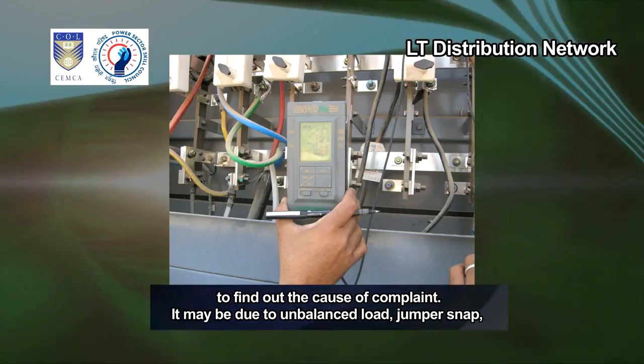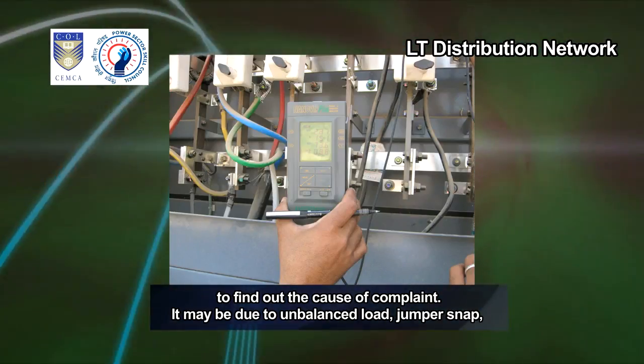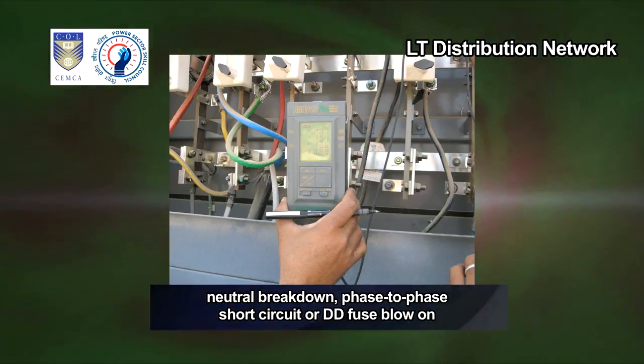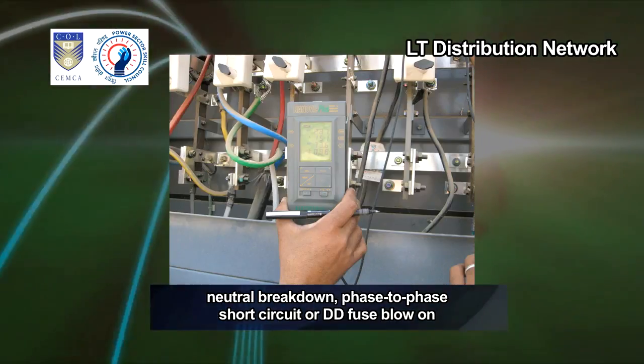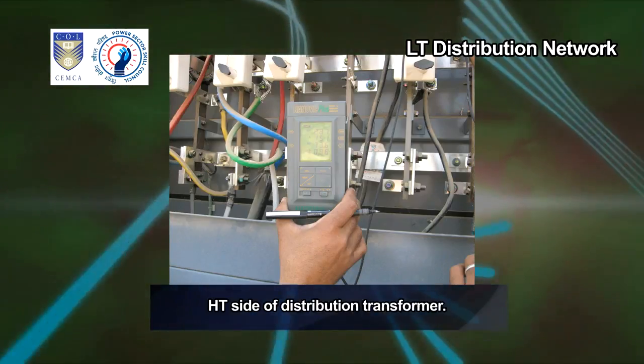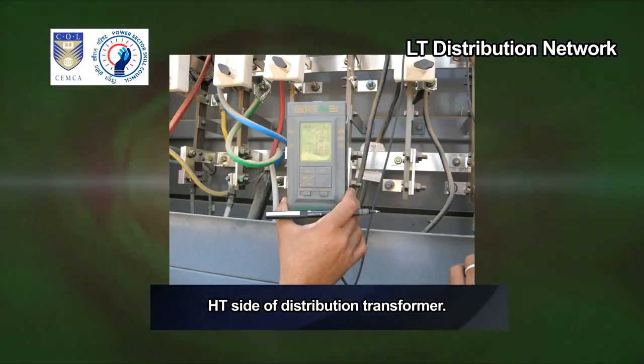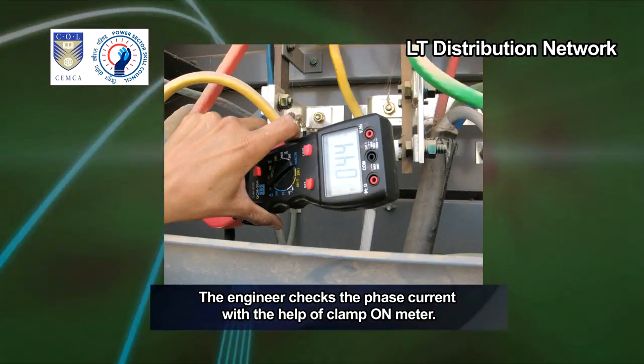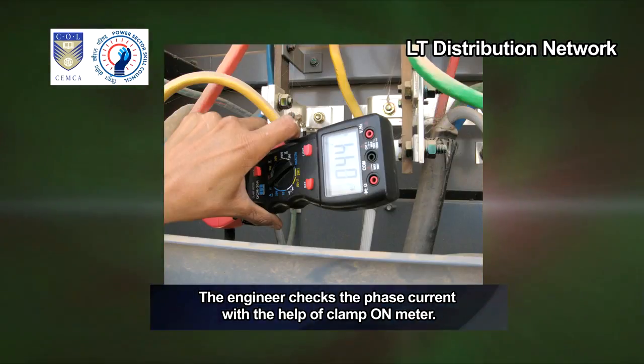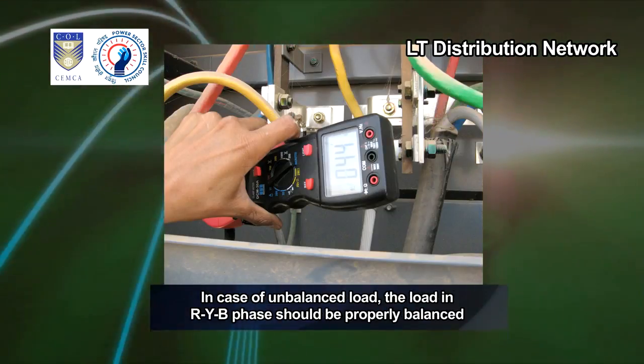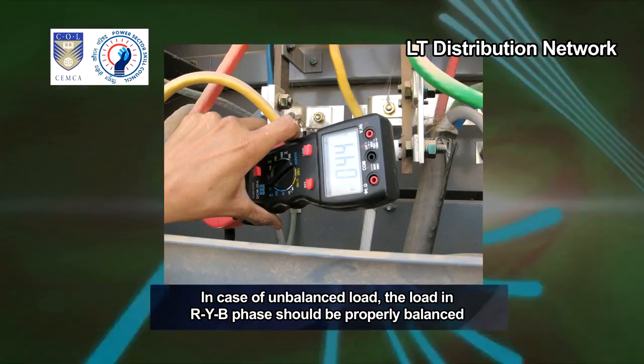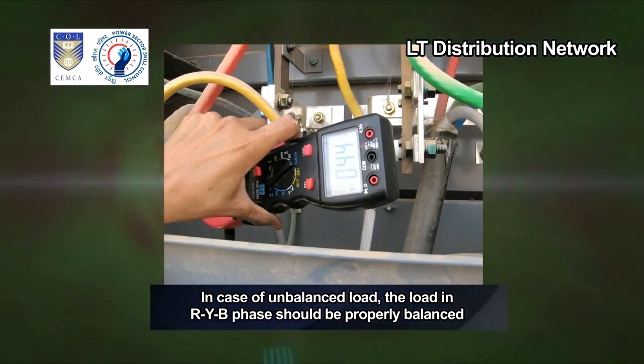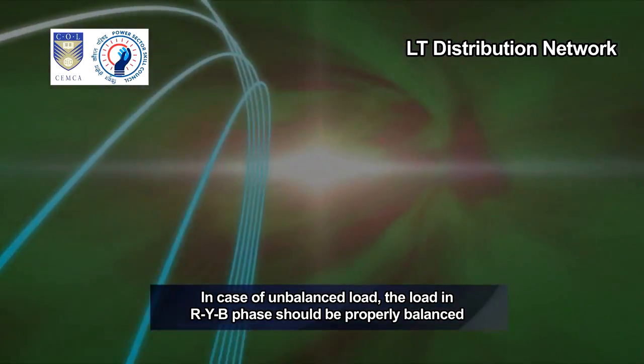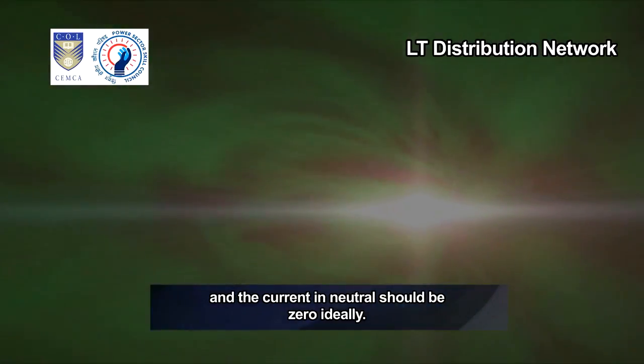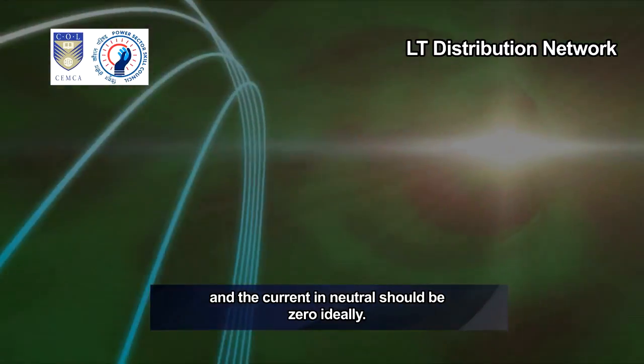It may be due to unbalanced load, jumper snap, neutral breakdown, phase-to-phase short circuit or DD fuse blow on HT side of distribution transformer. The engineer checks the phase current with the help of clamp-on meter. In case of unbalanced load, the load in RYB phase should be properly balanced and the current in neutral should be zero ideally.